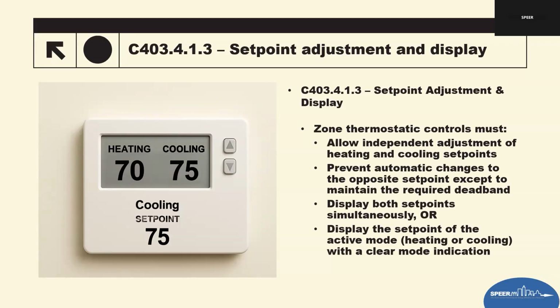C403.4.1.3 adds clarity on how thermostats must allow occupants or system operators to adjust heating and cooling set points. So these rules are closely tied to that deadband requirement we just went through. So we have independent adjustment required. Basically the code requires that the heating set point and cooling set point are independently adjustable.